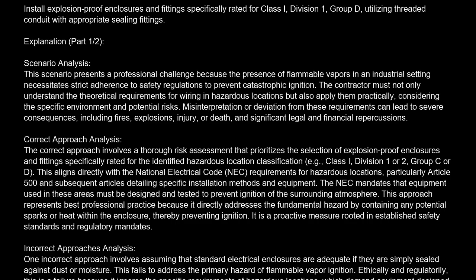Incorrect approaches analysis. One incorrect approach involves assuming that standard electrical enclosures are adequate if they are simply sealed against dust or moisture. This fails to address the primary hazard of flammable vapor ignition. Ethically and regulatorily, this is a failure because it ignores the specific requirements of hazardous locations, which demand equipment designed to contain explosions, not just resist environmental ingress.